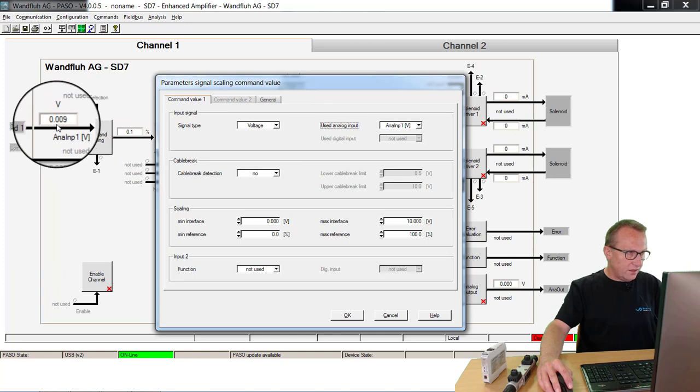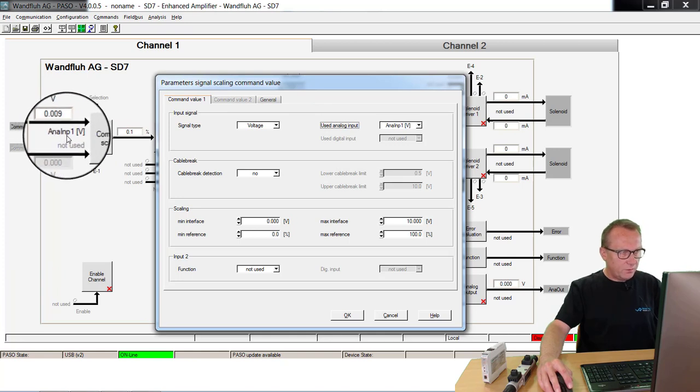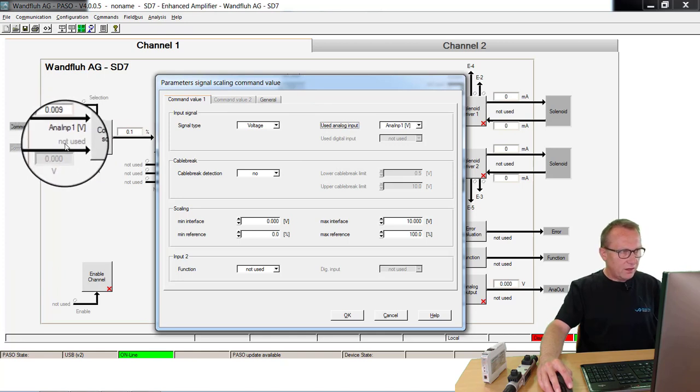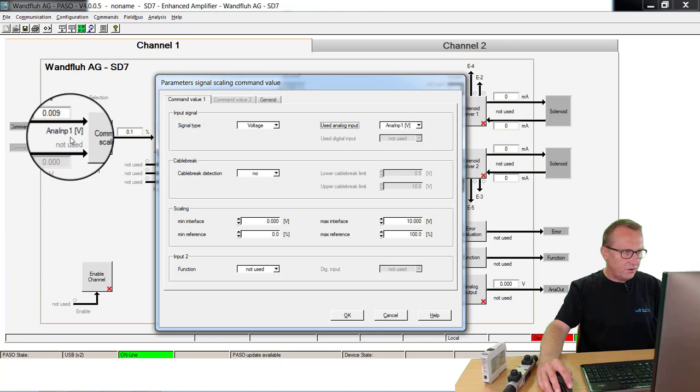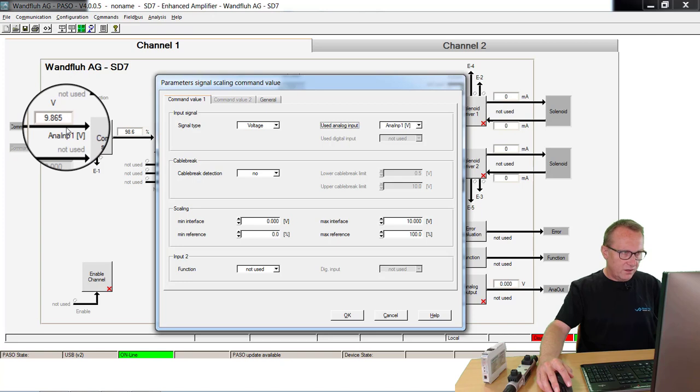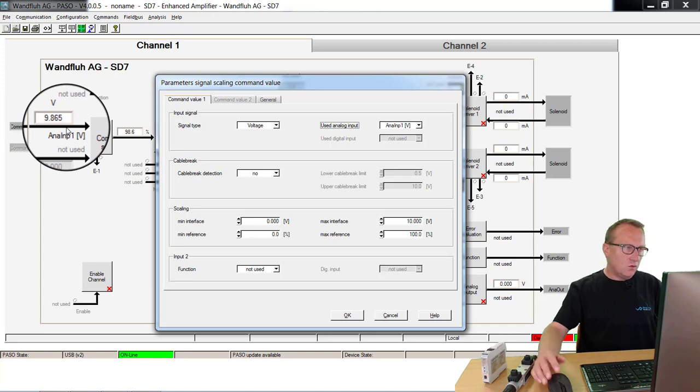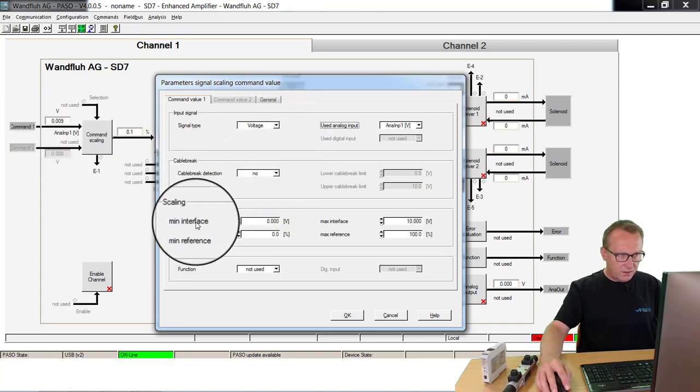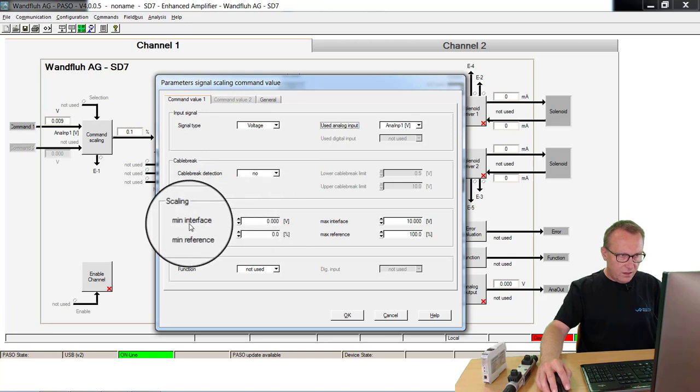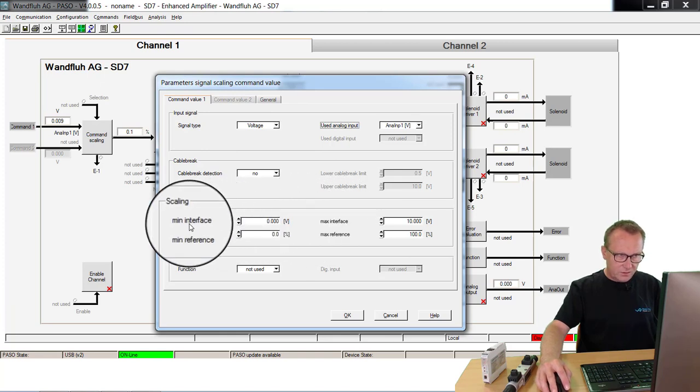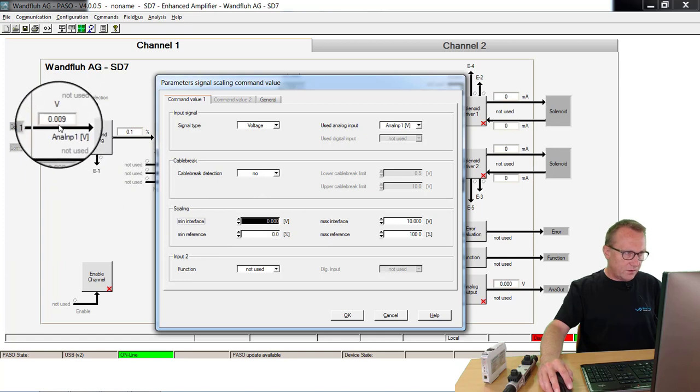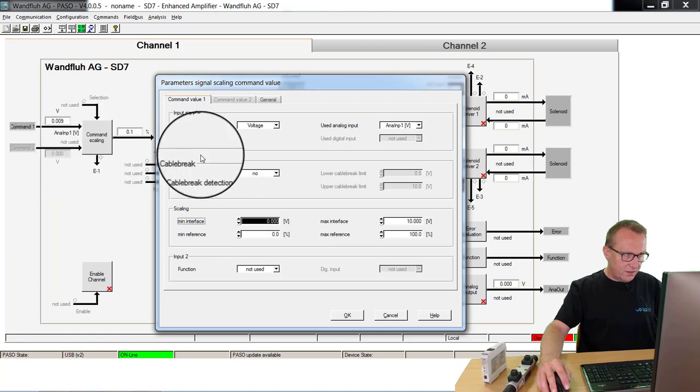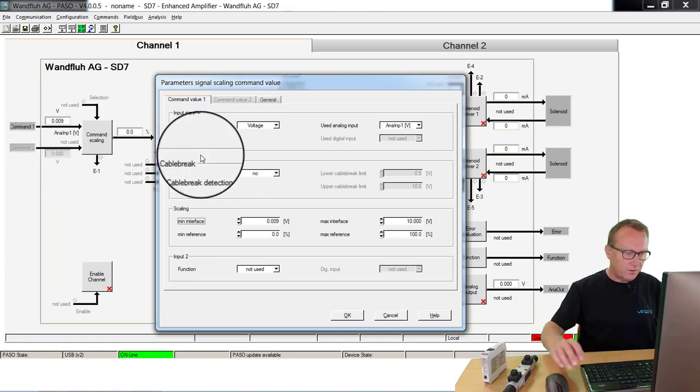Now you can see here the value. If the potentiometer is on the left side, I have nearly zero. If I turn the potentiometer to the right side, I have nearly 10V. These two values I have to set now inside here as the minimum interface and the maximum interface. The minimum interface, as you can see here, is 0.009V.